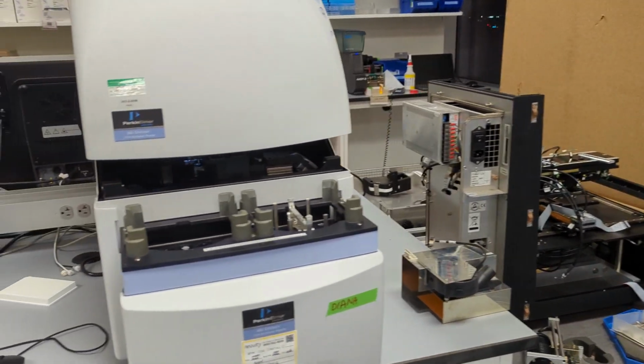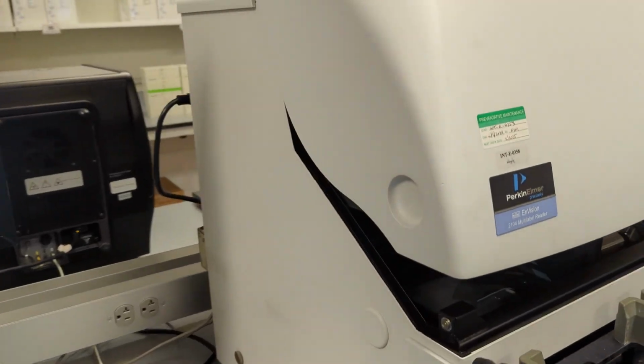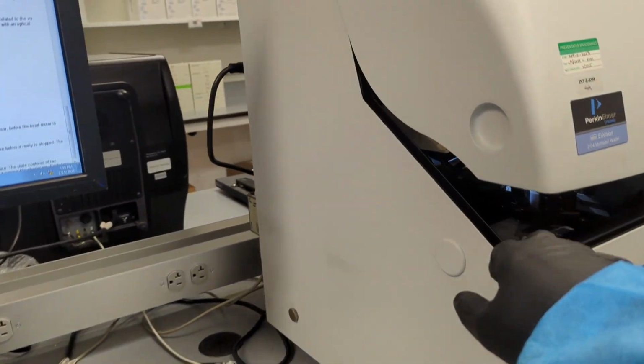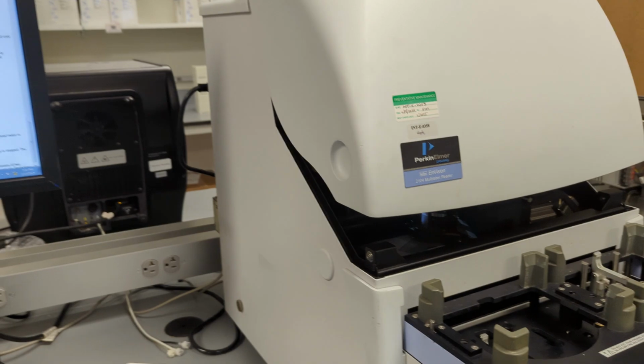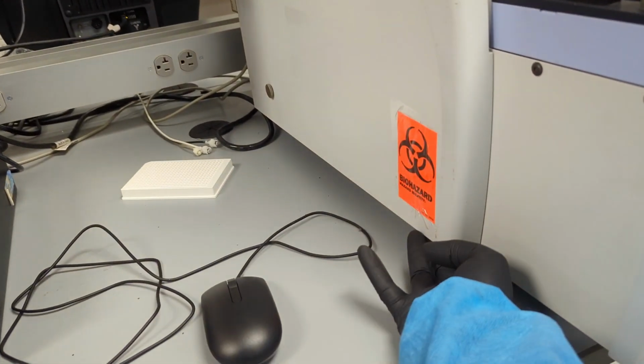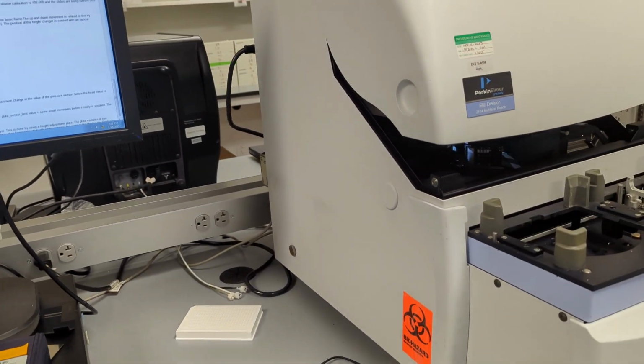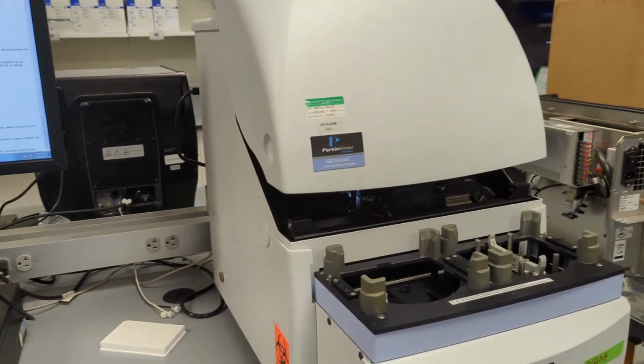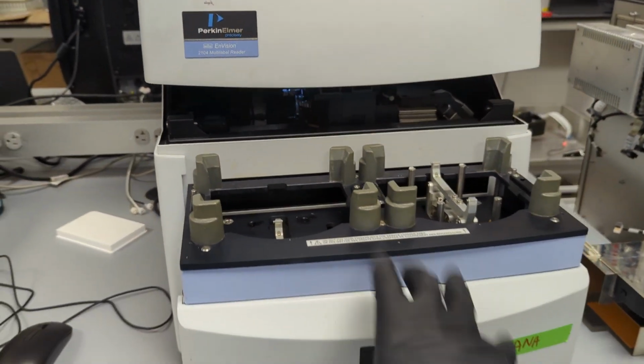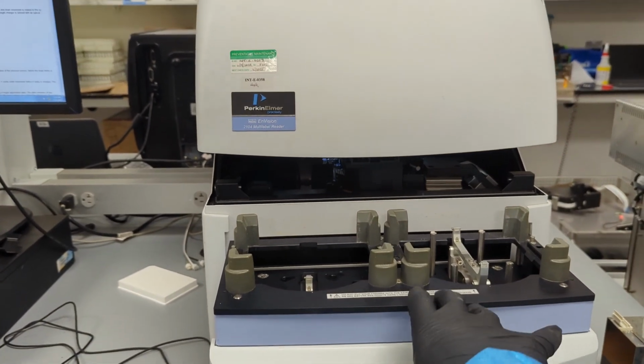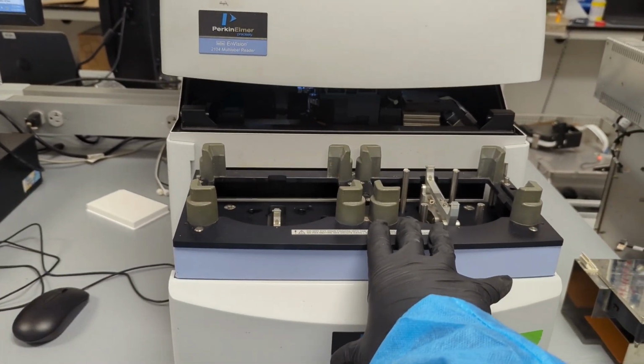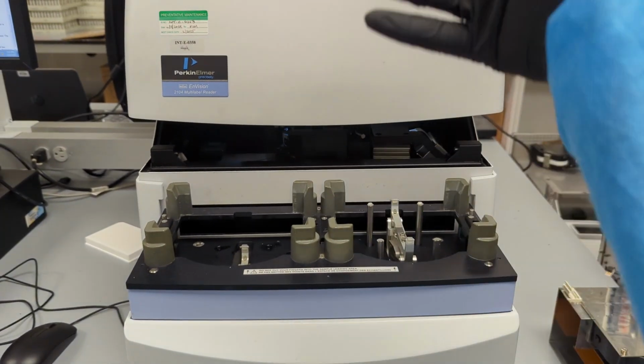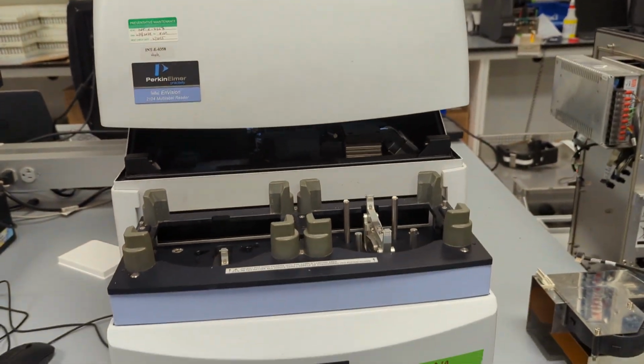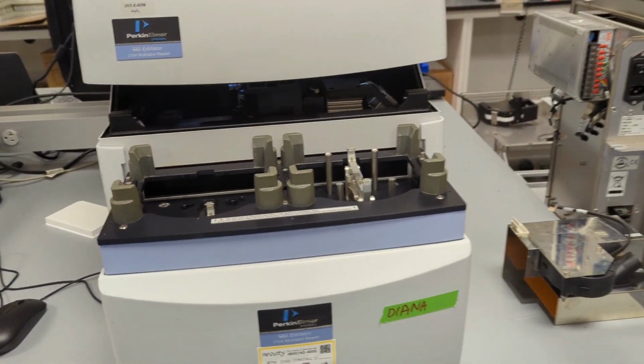One quick note for servicing these: this whole piece, this shell, actually comes off. There are some screws on the bottom and then in the back where you can literally pull this whole thing off to get easier access. You can pull this part off too. Yours might not come with this. If you own one of these, this is for feeding in plates. So you've got these towers that you can add. This is the plate stacker, that's what they call it, and it will automatically load plates if you have a number of plates to run. You can remove that as well.